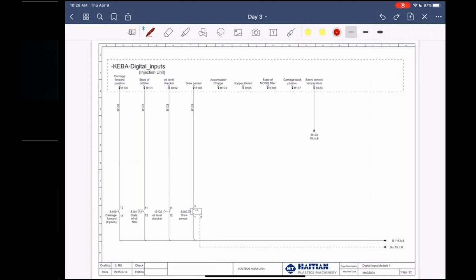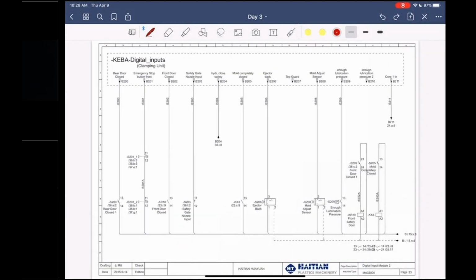And this is your digital inputs. So all your inputs are here. You have your carriage forward, which is an option, oil filter status, oil level, your screw rotate sensor. And over here you have your rear door closed, emergency stop, front door closed, safety gate nozzle, hydraulic safety, mold completely closed, ejector back, mold adjust sensor, enough lubrication pressure, and your core in. Down here you have your mold completely closed signal and your front door closed signal.